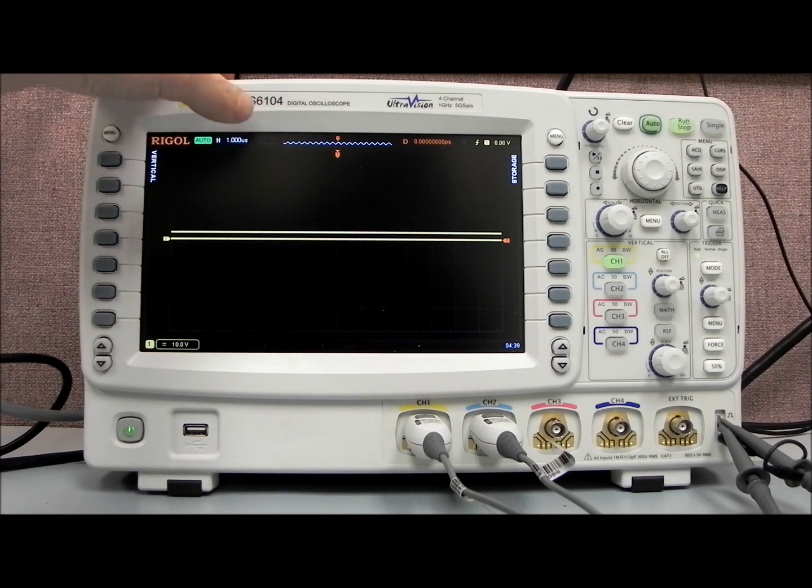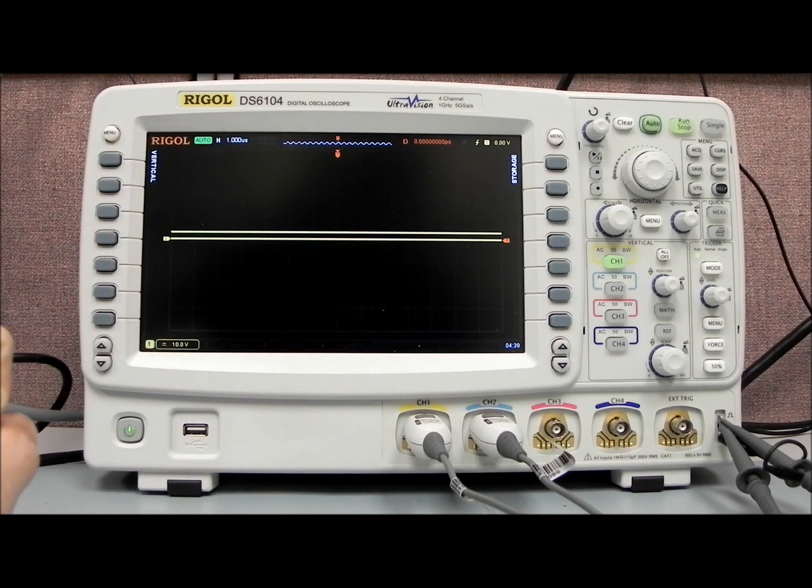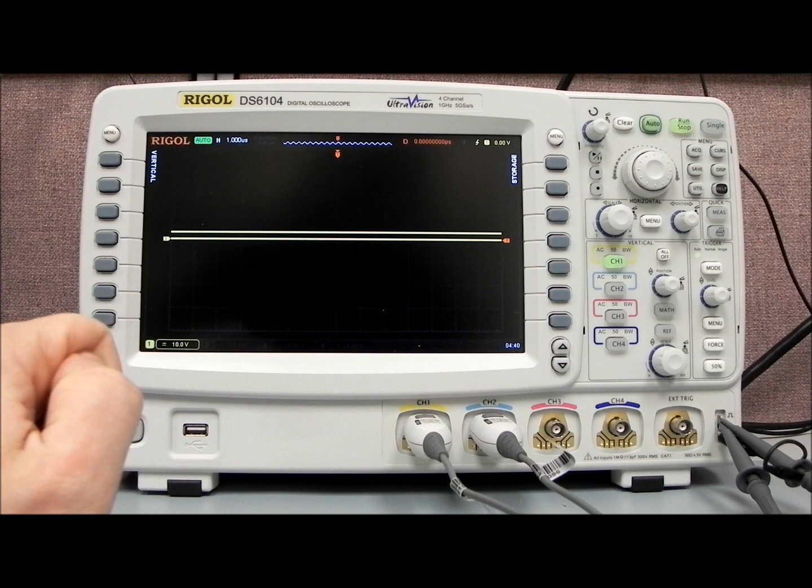Just to the right of that, we have the sample rate. In this case, it's 5 gigasamples per second. And then the number of data points that we're currently collecting per waveform, and that's set to 70,000 points.